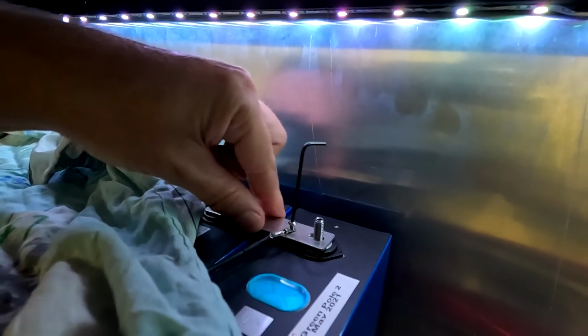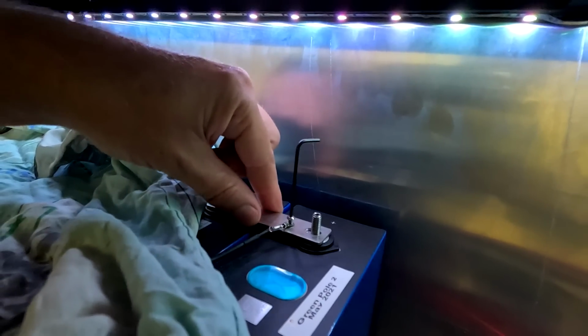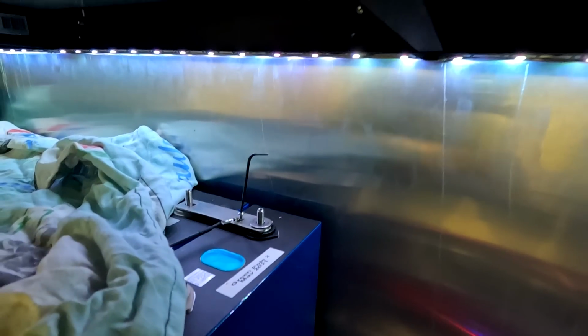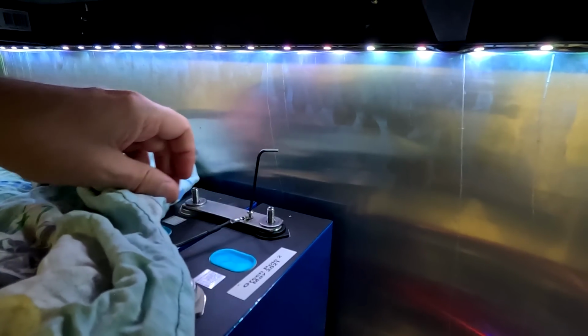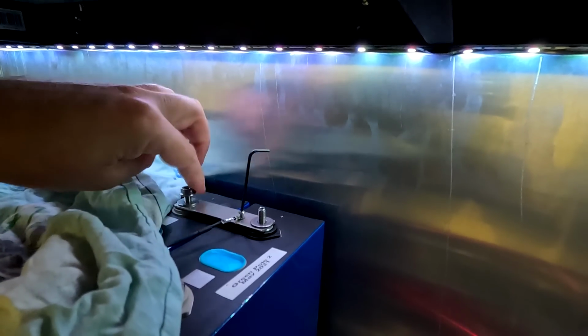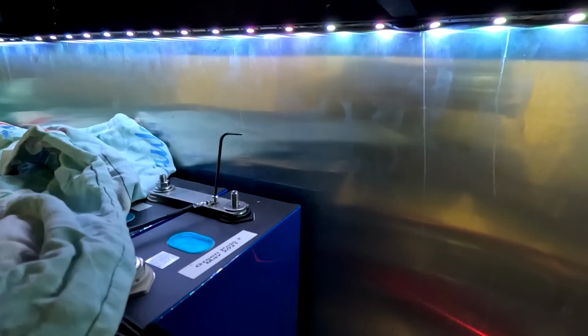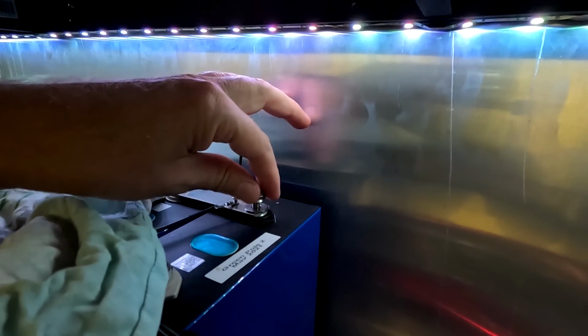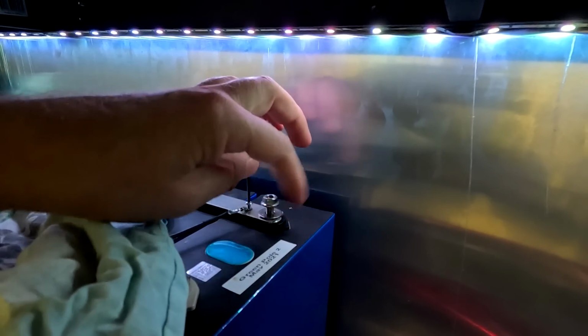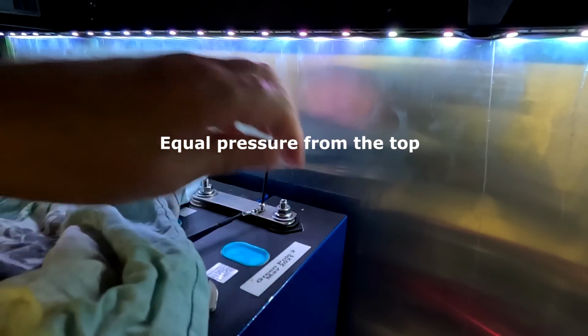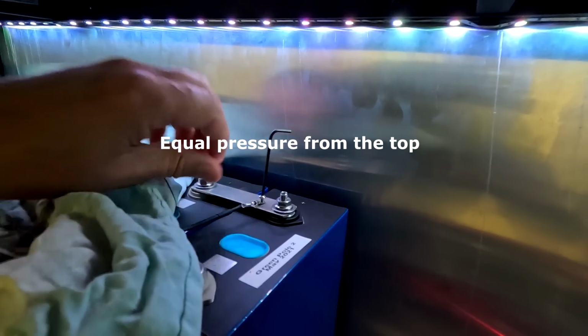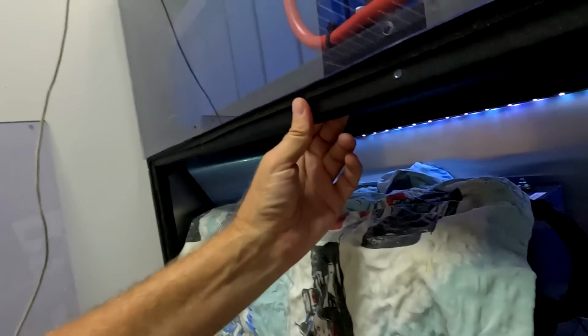See, we still have a bit of play here with the bus bar. Nice washer, flange nut. We don't actually need the washers, but I'll leave them on since they don't cause harm and give us a bit more contact area from the top. At the far end we'll torque all these connections to 4 Newton meters again, as they were before.